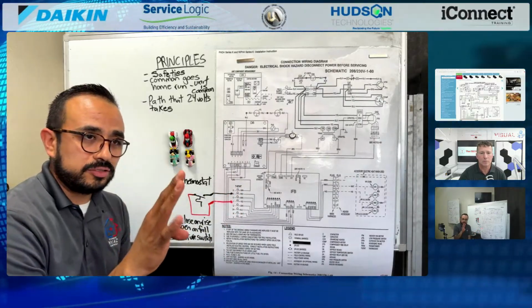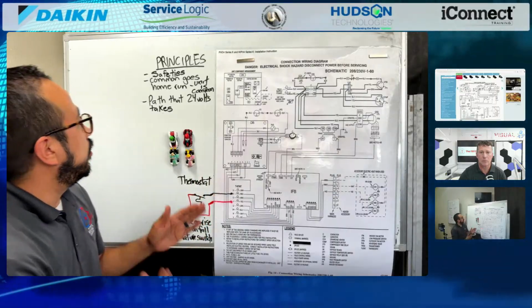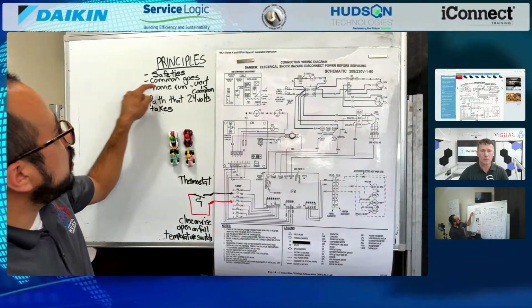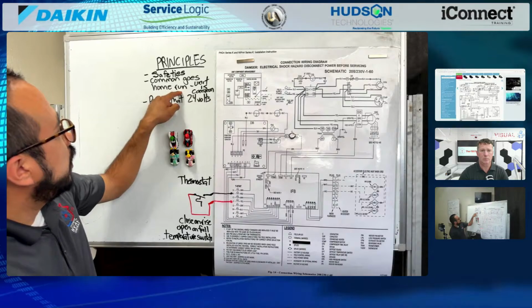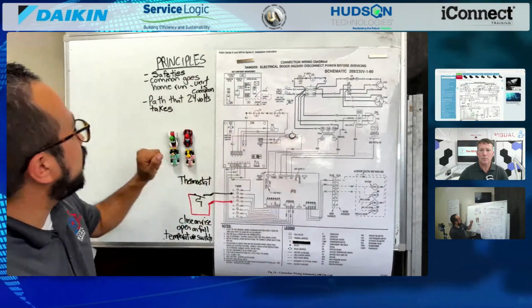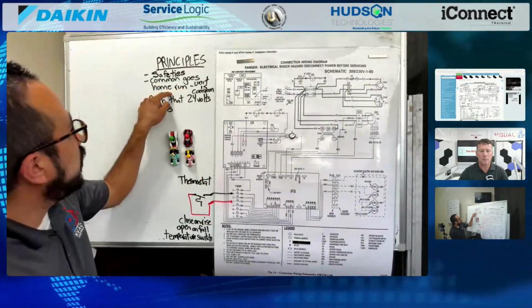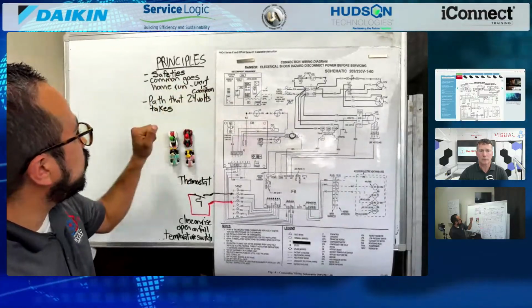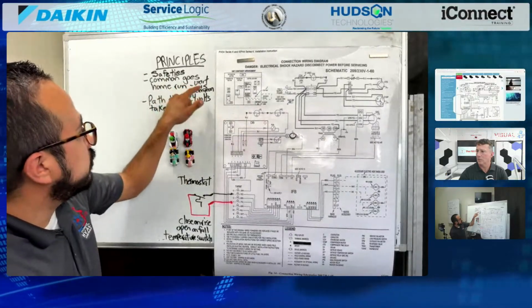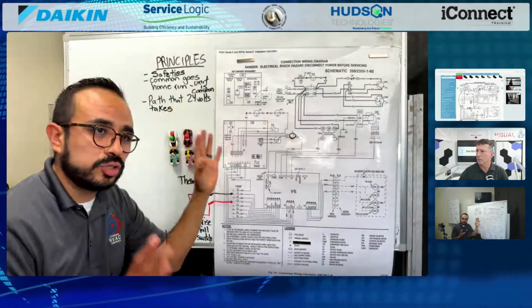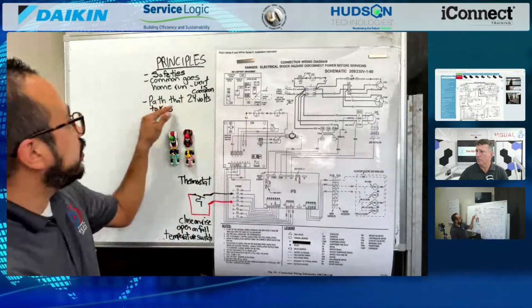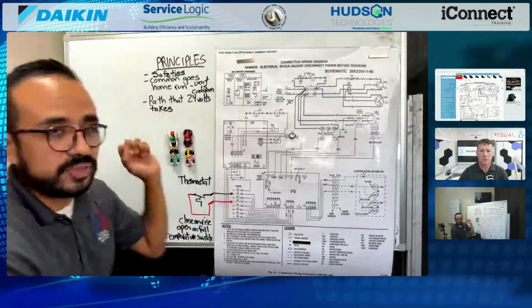There are 4 principles. One is: common goes home run. I'll explain what I mean by that. Common goes home run—in this case, to my contactor coil, my unit is common—and that's good for troubleshooting the path that 24 volts takes, and then your safeties.